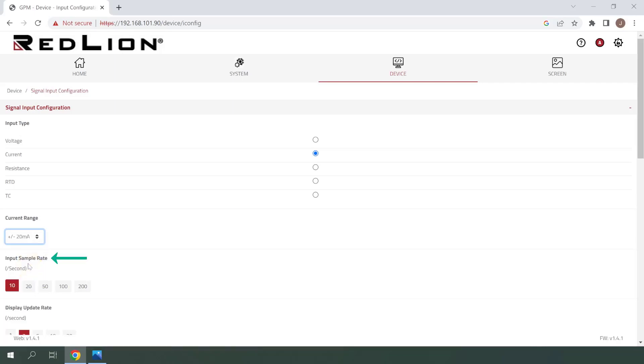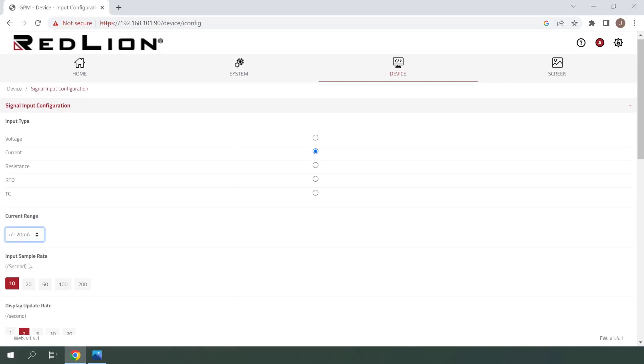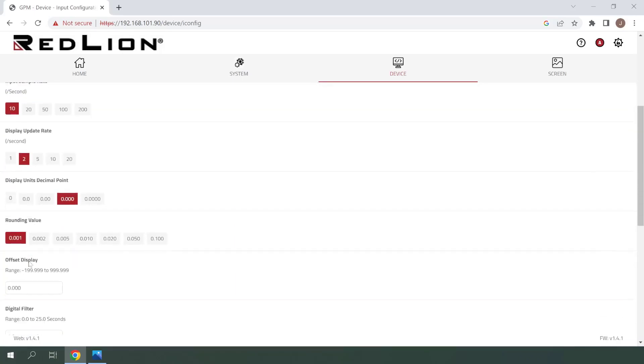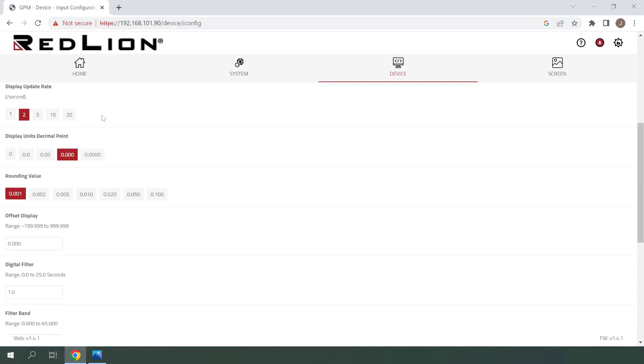Input sample rate is the number of times per second that the input is measured. I'll be leaving this at 10 samples per second, which will be plenty fast for this demonstration. Display update rate is the number of times the measured value is updated on the physical display per second. This won't affect the update rate of our web browser, so I'll leave this at 2 times per second.